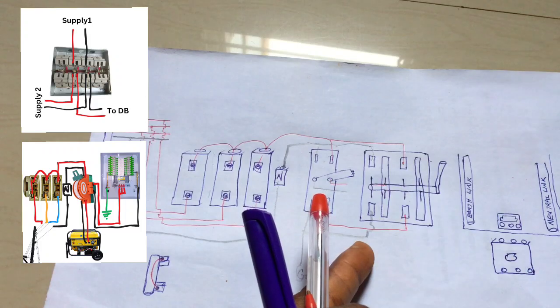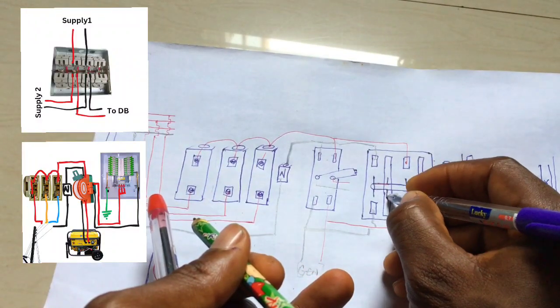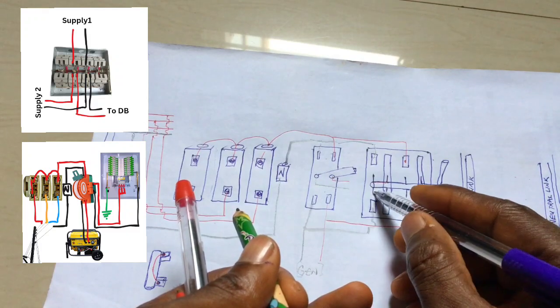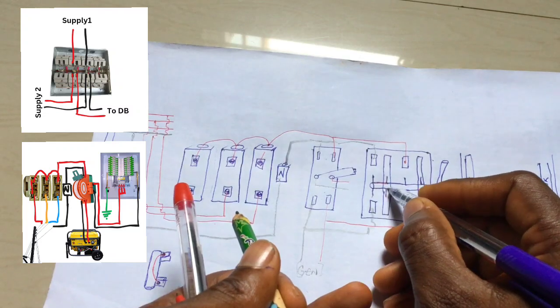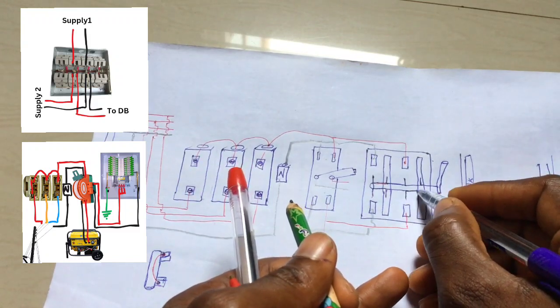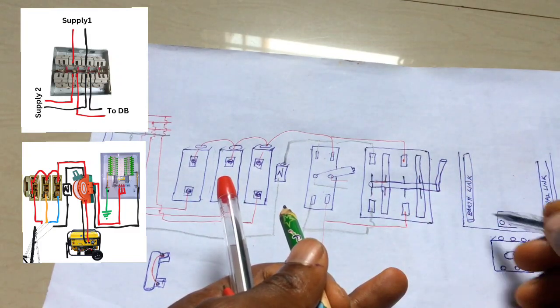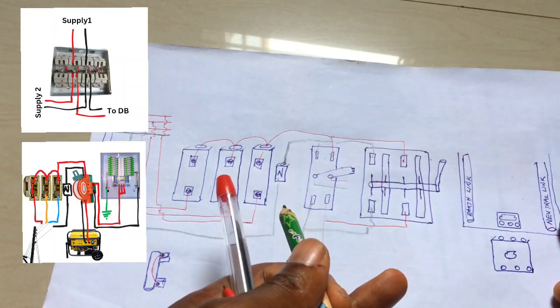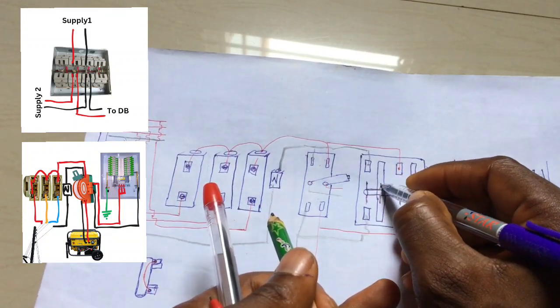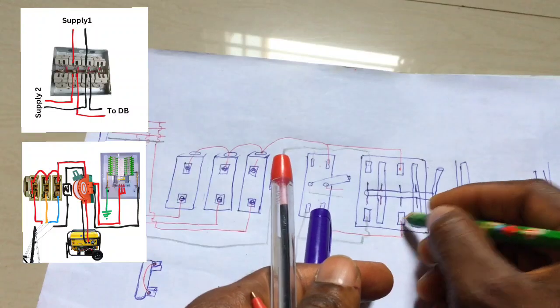If we want to use the generator and it is supplied, you bring the gear down. There is a conductive part in this gear that bridges the input and output terminals. Once you bring the gear down it creates contact — it closes neutral from the input to the output going to our building, and equally closes live from the input to the output going to our building. The same happens with the public grid — push the gear up and power flows to the building.